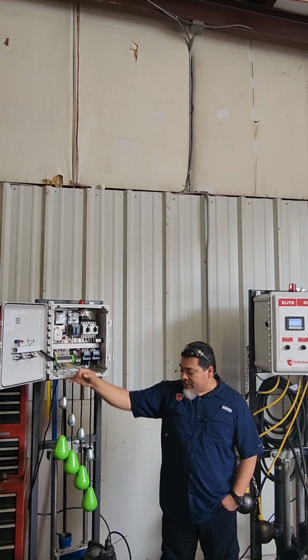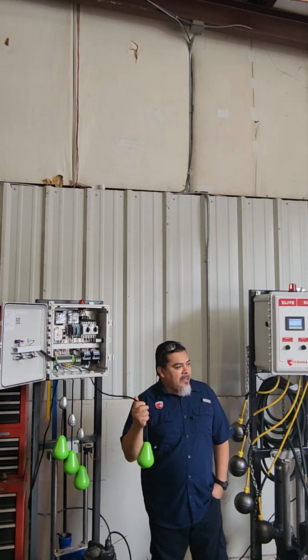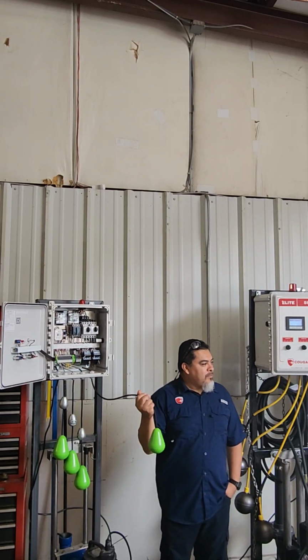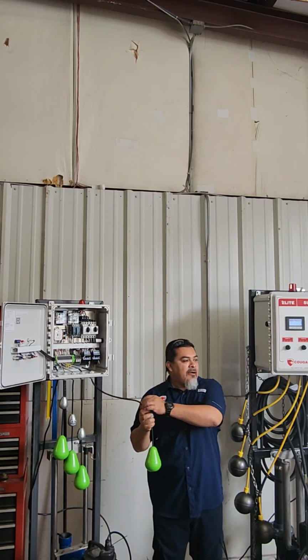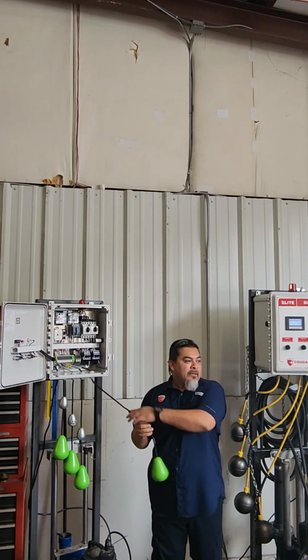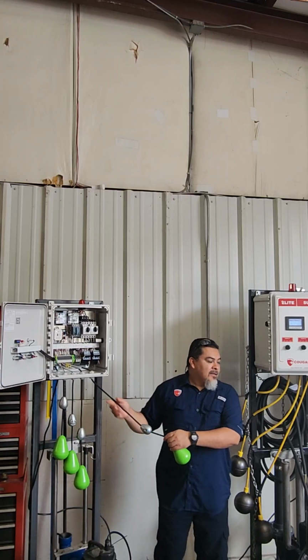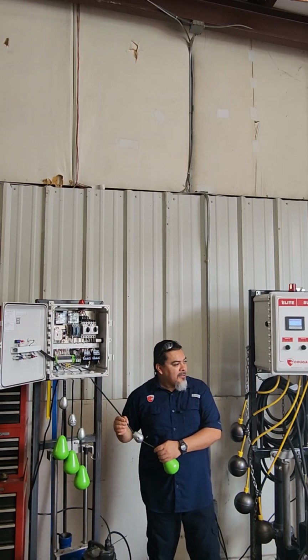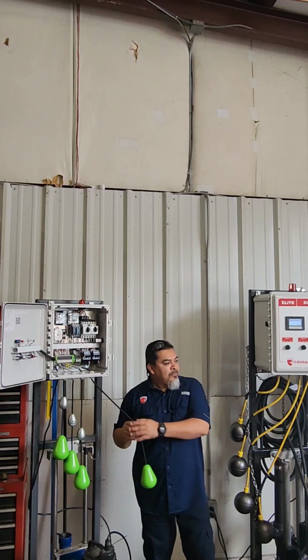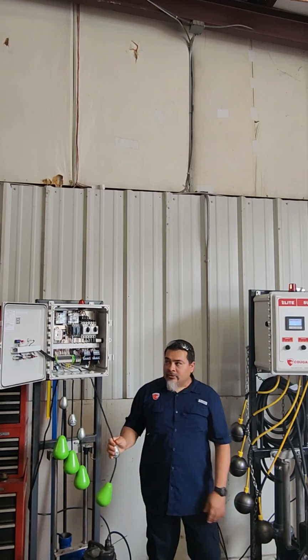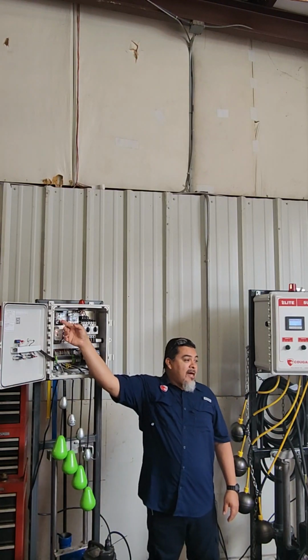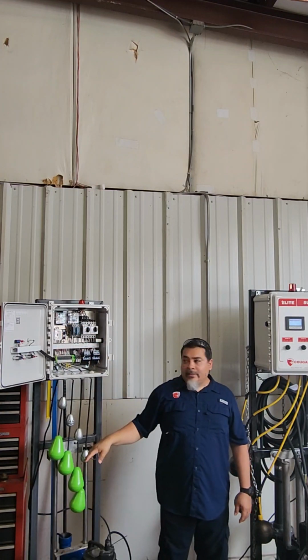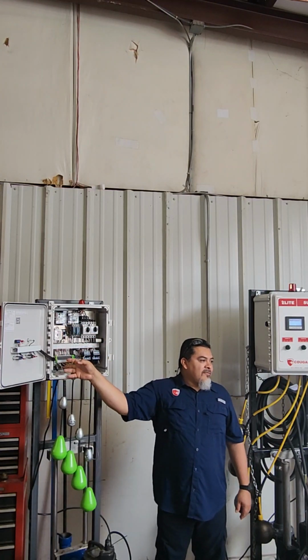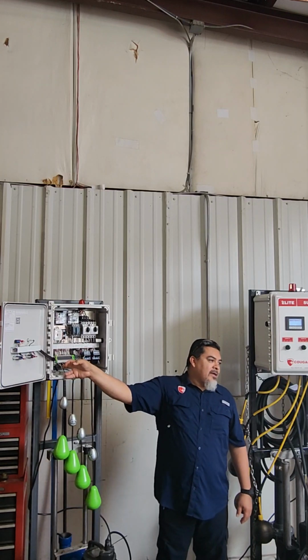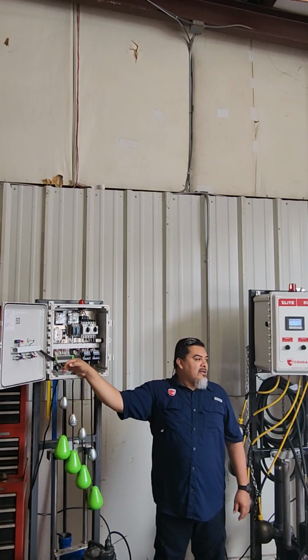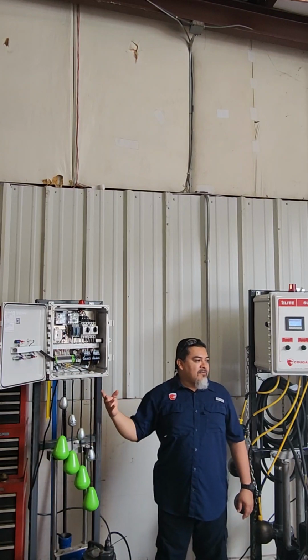There are cases where you see the floats and the cable is swollen, more likely it's a crack in there, and the floats have a paper inside or some kind of nylon that, what they was telling you, starts sucking the water in. So then this gets swollen and starts causing a direct short. So if you start getting the control fuse being blown a lot, you can start disconnecting a few floats. I always go by that. If you don't know where the issue's at, start disconnecting the floats and verify to see if you still blow a fuse.